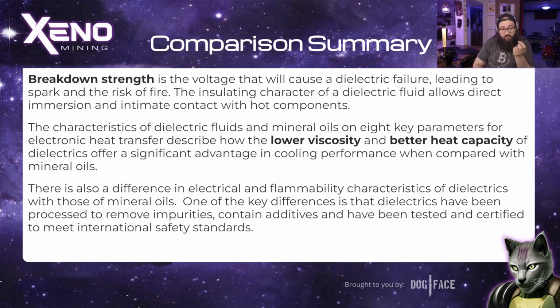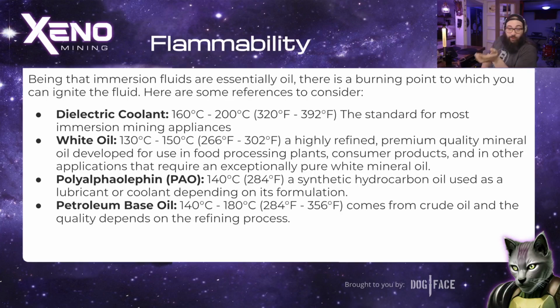This is why, going back to white oil, petroleum-based oil, or polyalpha olefin PAO, if we get these kinds of oils, they're more likely to respond to that sort of heat from a voltage spike, which is one of the reasons why, for safety, dielectric coolant is much better across the span of this stuff.